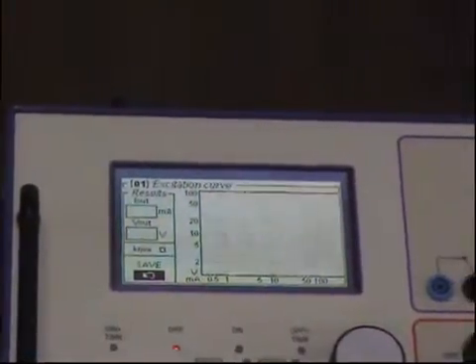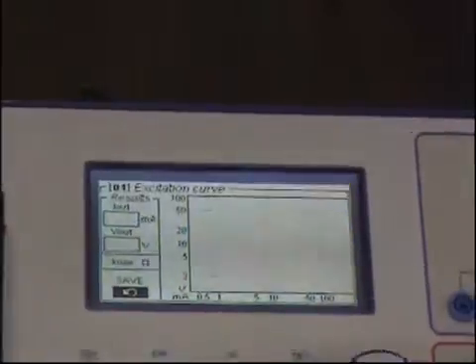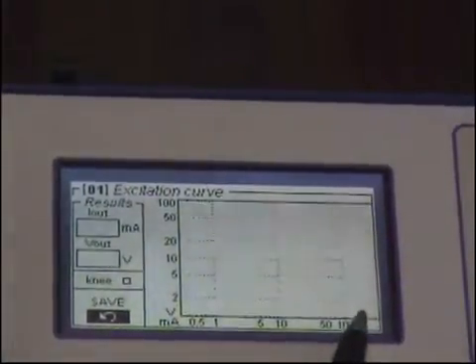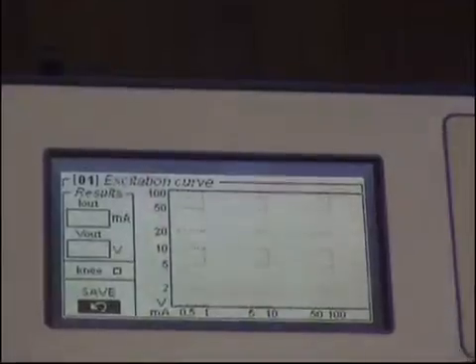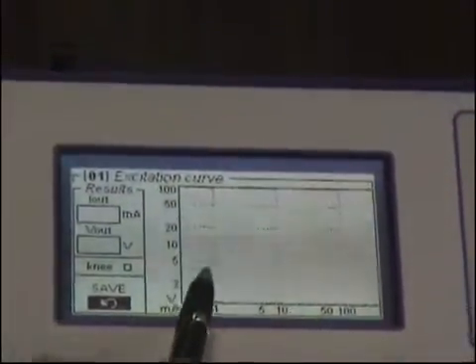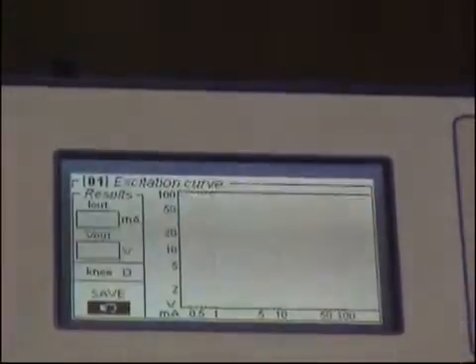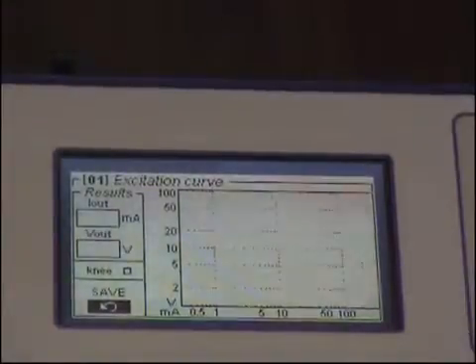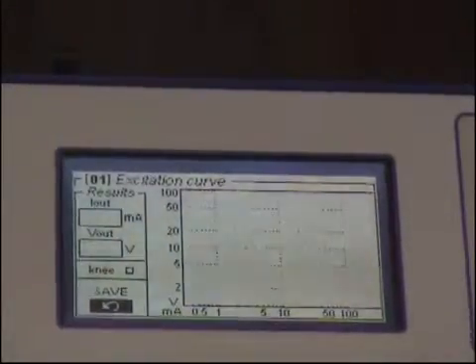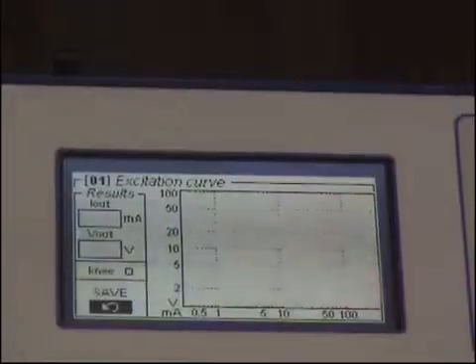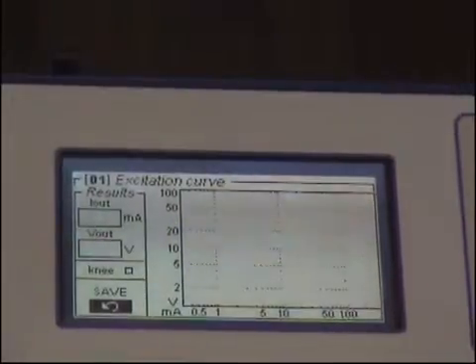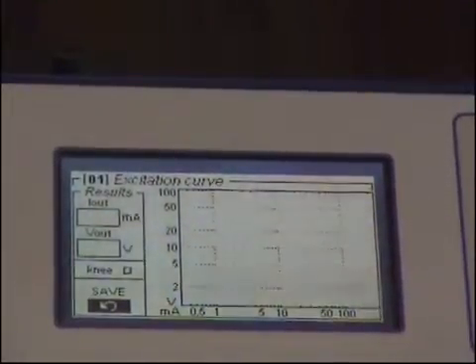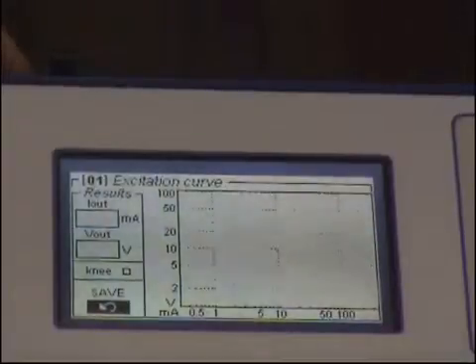As I press test, the next screen shows milli amps versus volts. On this screen we will see the saturation curve of the current transformer growing as we increase the current. There is one important thing to say.